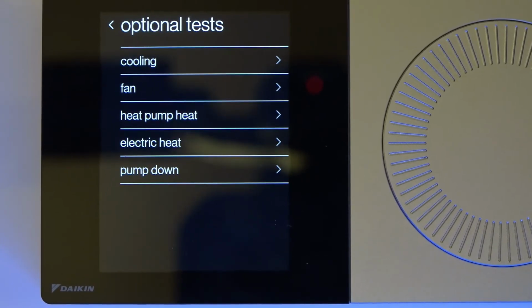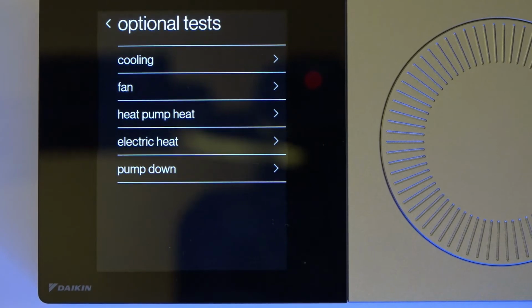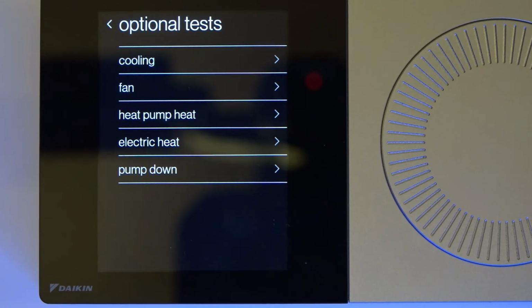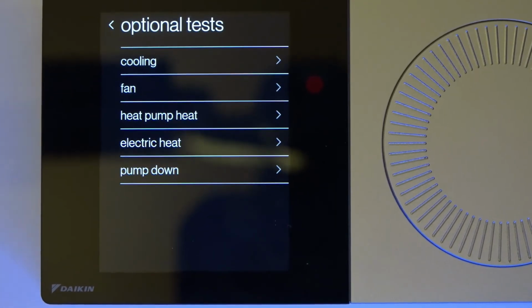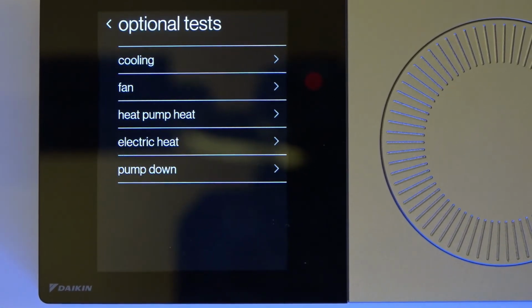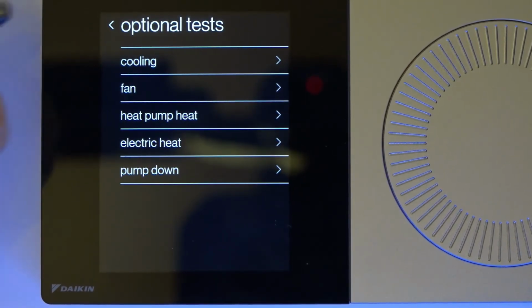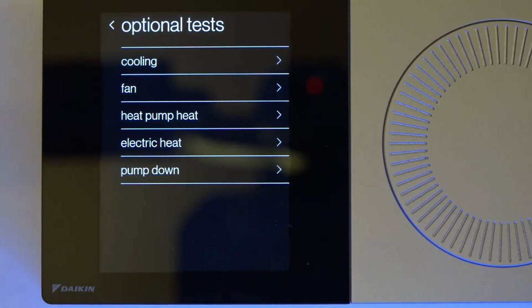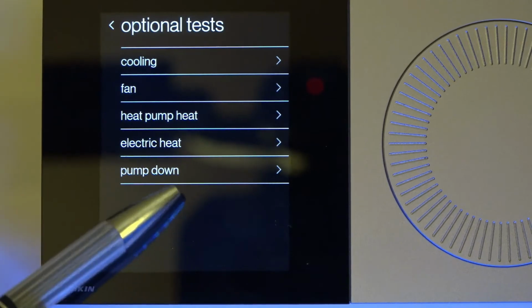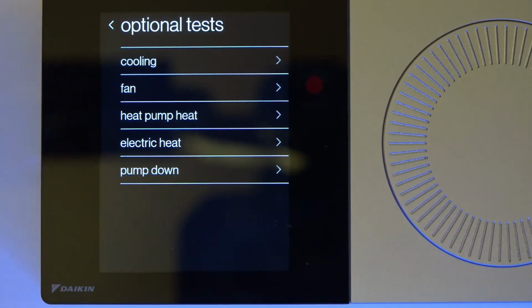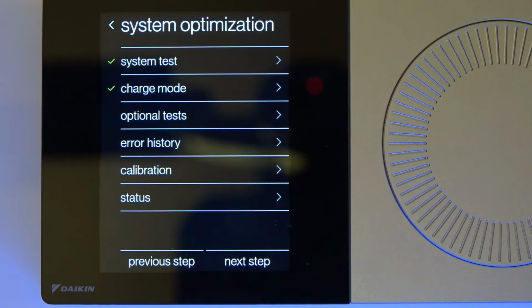And also, since there's no contactor on this board to energize the compressor, this allows me to electronically send a signal to start the compressor. So this is the only way to pump down the system is here. If you ever have to pump it down, do not close the liquid line until after the compressor is started. So those are your optional tests. Now if I've added equipment like a dehumidifier or a humidifier, it would give me the options to be able to test those as well.